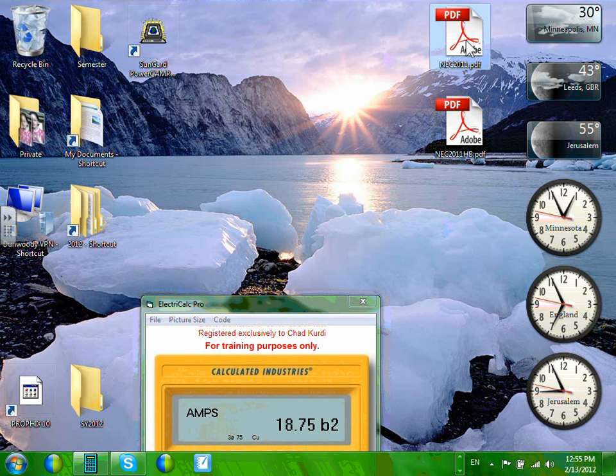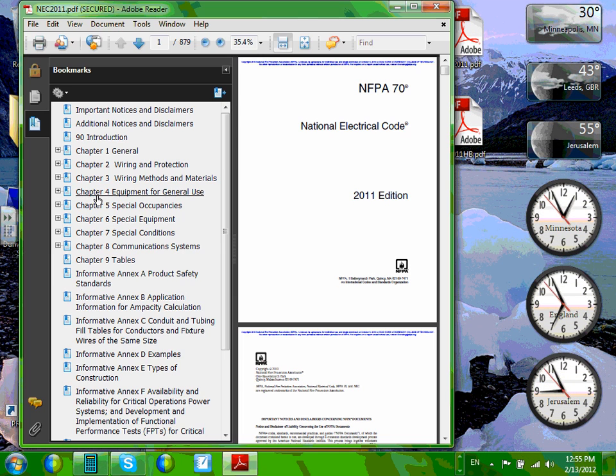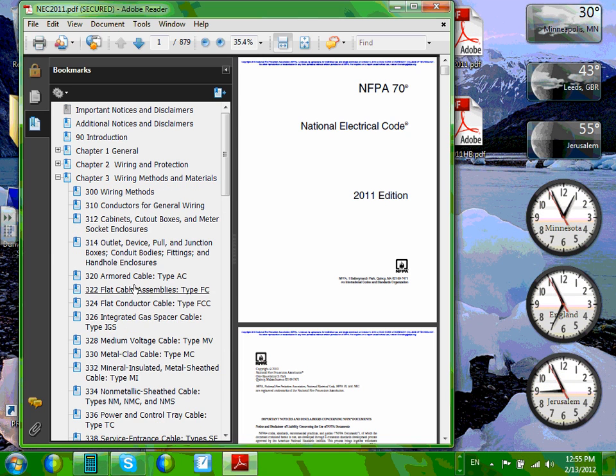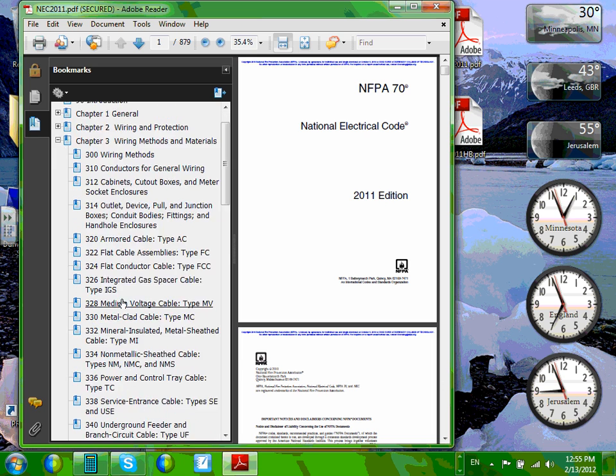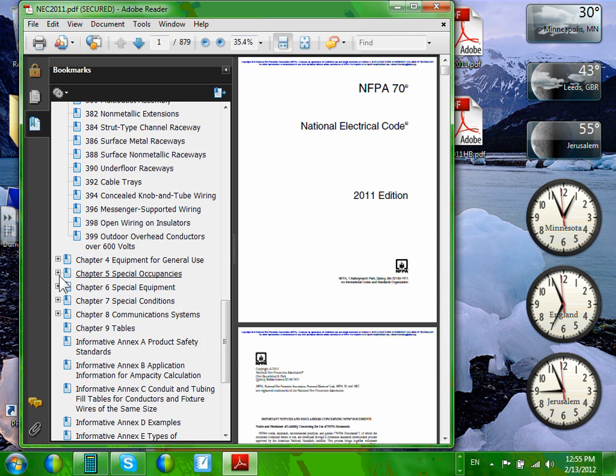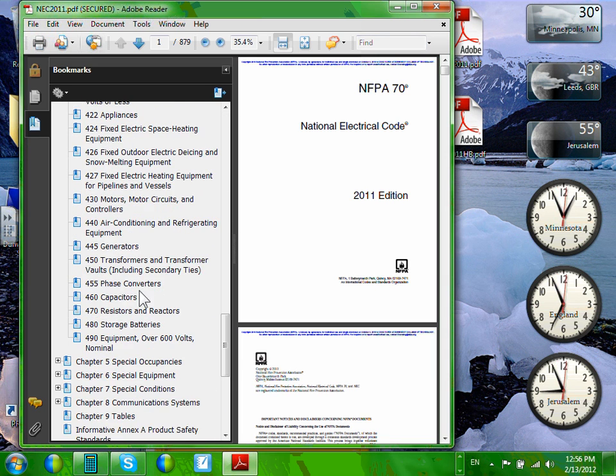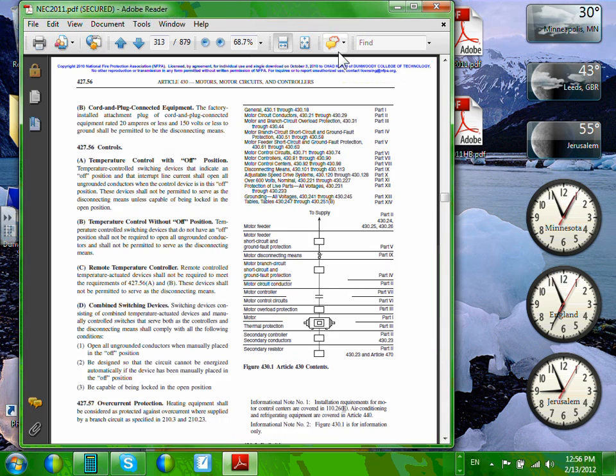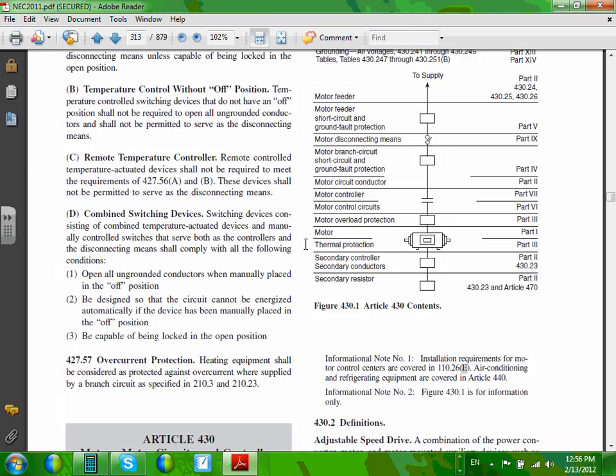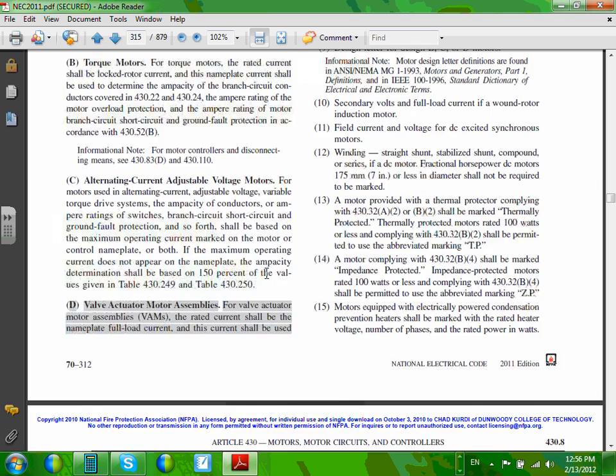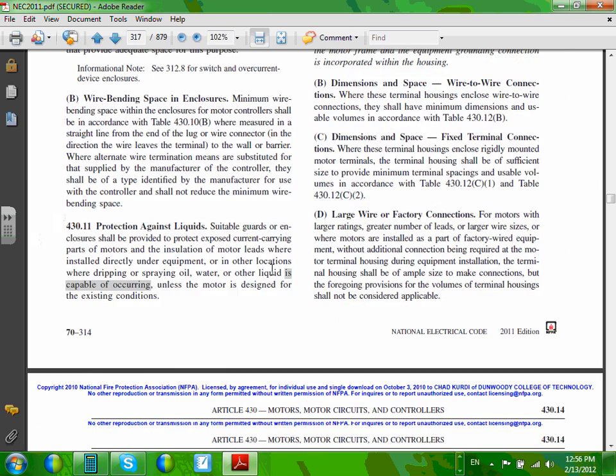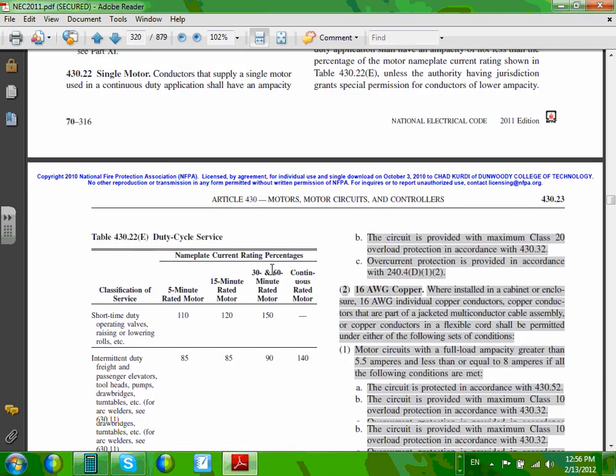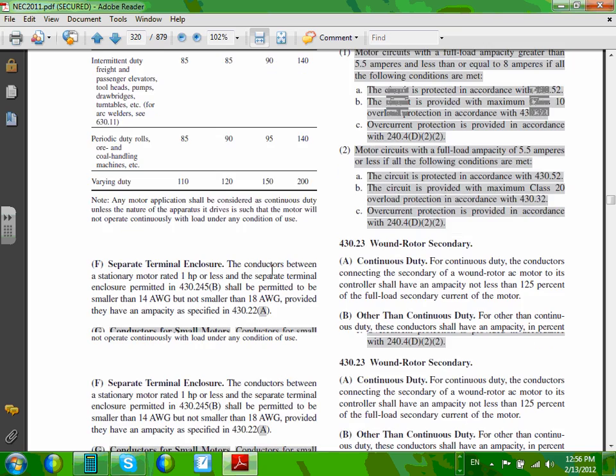Here's my NEC code book. Let's go back to the mother, to the source, right? Because we all go by the code. Let's go to the motors. If we go to the motors, Article 430, what am I here, Chad? Article 430. Okay, if you go to Article 430, let's go all the way to the overcurrent protection device. The table that says about the overcurrent protection, right here. No, not right here. It should tell you.